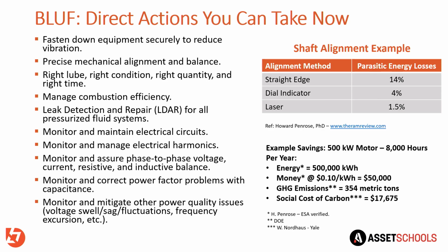Howard's doing a lot of writing in this area, and he's had a lot of success with the use of passive harmonic filters. Another thing that he said is if you've got active harmonic filters, because you have little deviations in the voltage, the phase doesn't change, but you have deviations in what the offset should be because it changes in real time. Your actual active filters are fixed. So if you've got X number of amps here and it's deviating, but your offset is fixed, so that energy's got to go somewhere, and it makes its way to the ground and to your neutral loop. So take a look at that.